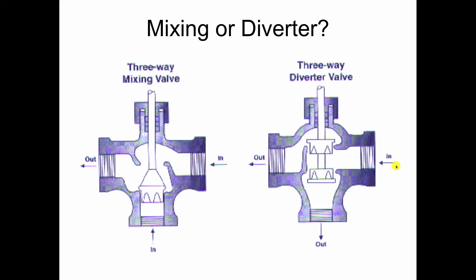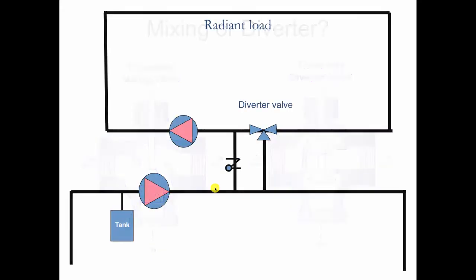This is a diverter valve which has one way in and two ways out. And by using this, which looks the same on the outside but works a little different internally, we're able to move the diverter valve over here. So your continuous radiant circuit is going around that way, your primary is going around that way.